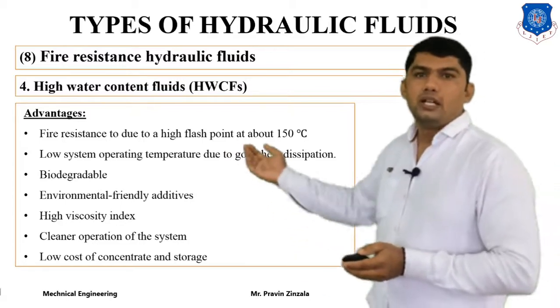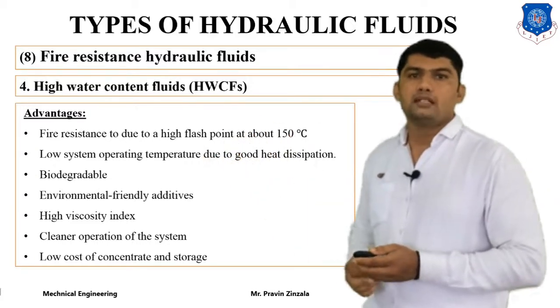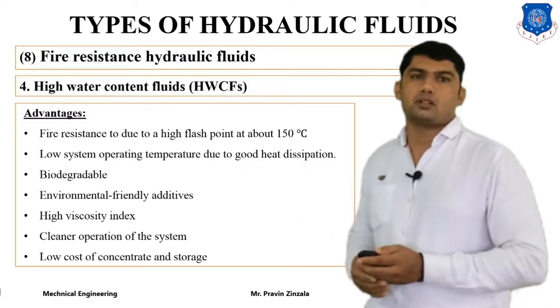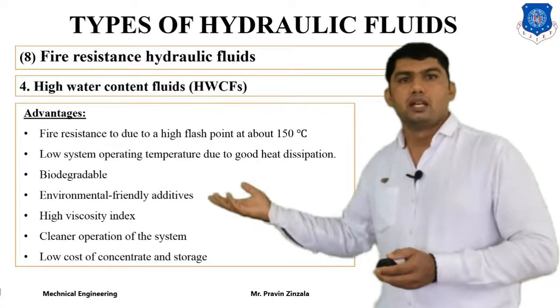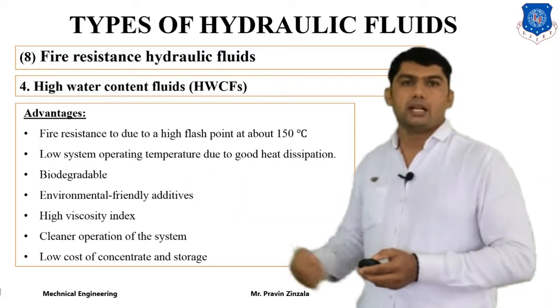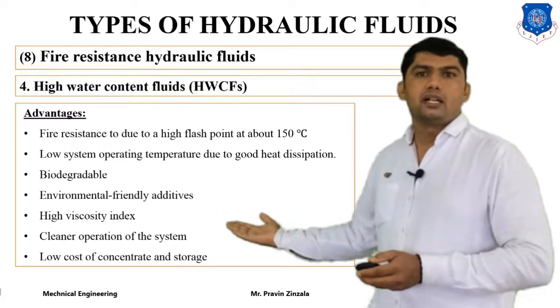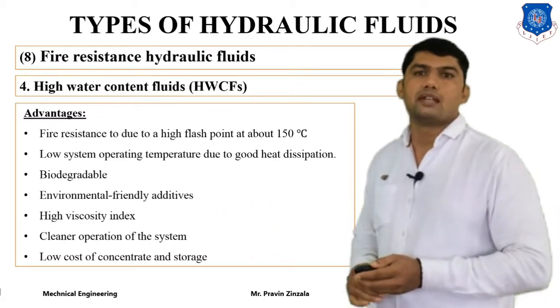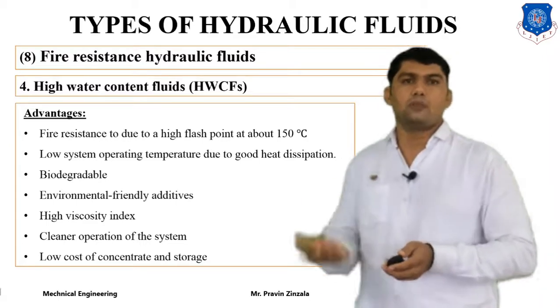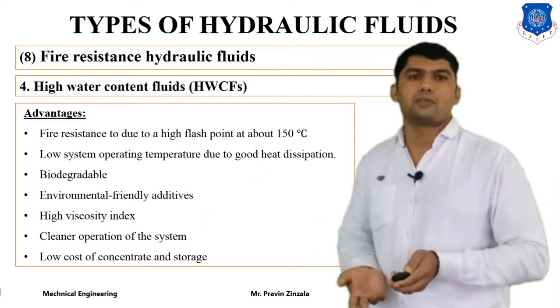The main advantages of high water content fluid: it is fire resistant because it uses a maximum quantity of water — about 90% water — its flash point is near 150 degrees centigrade, and it has low system operating temperature due to heat dissipation from the high water content. It is also biodegradable and environmentally friendly, has a high viscosity index, clean system operation, and low cost of concentration and storage. Leakage can easily be compensated by adding water up to 90% concentration.